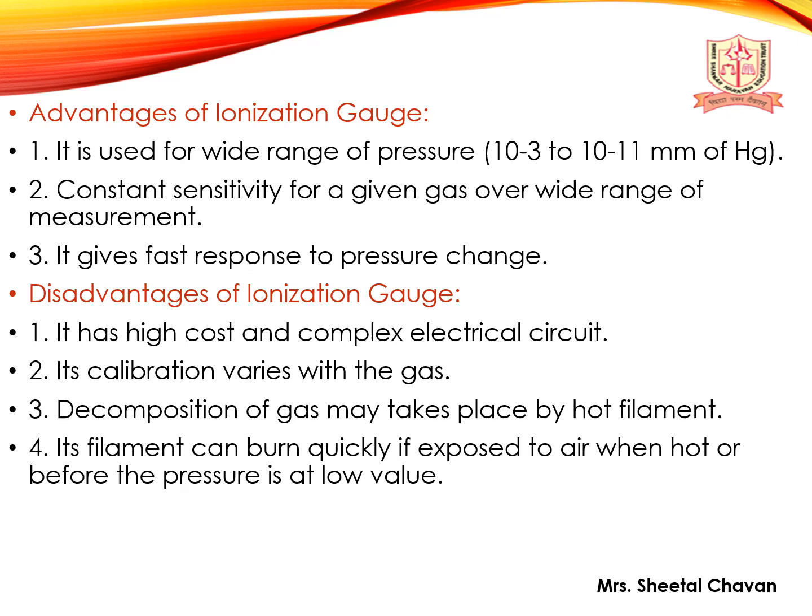Disadvantages of the ionization gauge. It has a high cost and a complex electrical circuit. Its calibration varies with the gas. Decomposition of gas may take place at the hot filament. Its filament can burn out quickly if exposed to air when hot or before the pressure is at a low value.